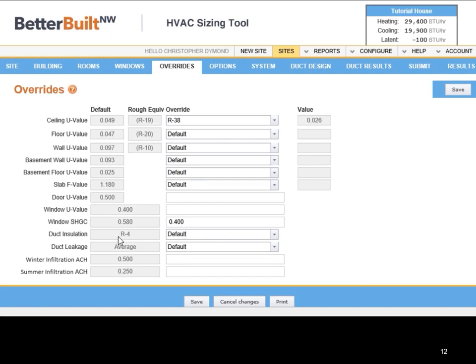In the Northwest, you'll generally find that the U value and the solar heat gain coefficient march right along. If you happen to buy a Class 30 window, chances are the solar heat gain coefficient is going to be about 30 also. That can make a very big difference on the cooling load.